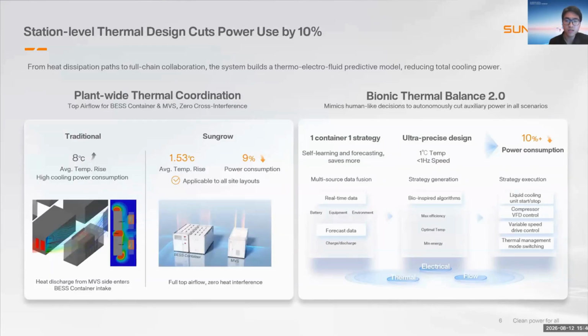And in terms of thermal management, our purpose is to reduce auxiliary power consumption. The system builds a thermo-electro-fluid coupled predictive model, which can optimize both system design and control strategy. At the system level, we adopt a plant-wide airflow coordination design. With the top airflow layout, the thermal interference between the MV station and the ESS is effectively reduced. Compared with traditional design, air inlet temperature rise is reduced from 8 degrees C to 1.5 degrees C, which can significantly reduce the cooling demand. In addition, with the bionic thermal balance technology, the system applies a one-site, one-strategy approach to dynamically optimize performance under different conditions. As a result, the auxiliary power consumption can be reduced by over 10%.